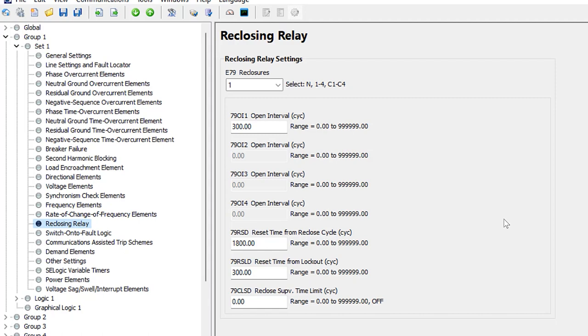For this example, we're implementing a reclosing scheme with three reclosing shots. The first thing to program is the enable for the reclosing scheme — setting E79. You can set this to NO for no reclosing, or 1 through 4 for different numbers of shots. We'll set this to 3. There's also a C1 through C4 option, which is the same as 1 through 4 except that if the reclose supervision is not met, the scheme proceeds to the next shot instead of going to lockout — this mimics older electromechanical reclosing relays. We won't use that for this example.